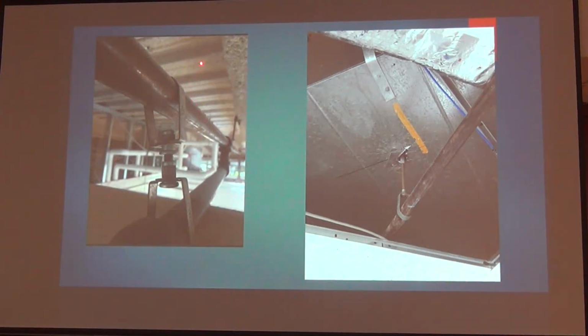That auto grip nut is definitely upside down, and as the building moves and shakes, it's gonna fall off. This is where your eyes are important. I carry that stick with me, and I carry a very good flashlight. I don't like to get up on ladders. I will do it if I have to. I'm not afraid of heights. It's just a pain in the butt to carry it around the job site.